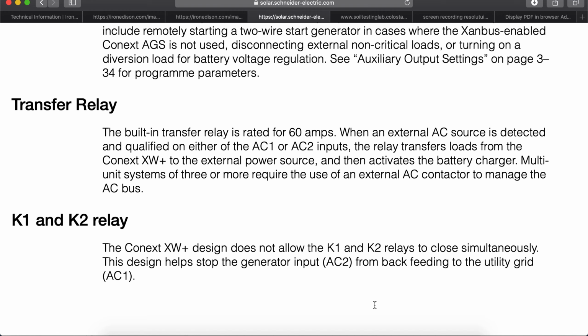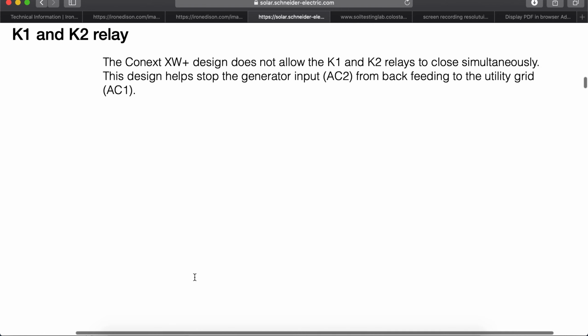Multi-unit systems of 3 or more require the use of an external contactor to manage the AC bus. The Conext XW Plus design does not allow the K1 and K2 relays to close simultaneously. This design helps stop generator input, AC2, from feeding back to the utility, AC1. Good design.